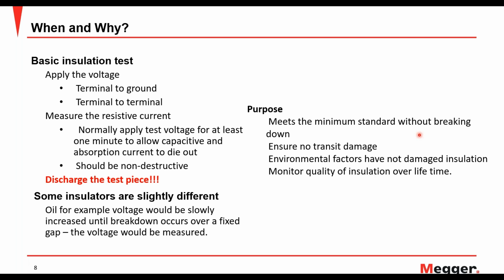Ensure there is no transit damage, specifically when transformers are transported to different locations, sent out by the manufacturers. A lot of times they are damaged during transport or while loading and unloading. There's a lot of chances that it might get damaged during transit, so definitely you're checking for that aspect. Also, make sure environmental factors have not damaged the insulation. Those play a big role. When you are commissioning a transformer, you want to make sure there's no moisture or dirt sitting on the bushings or contacts or whatever.